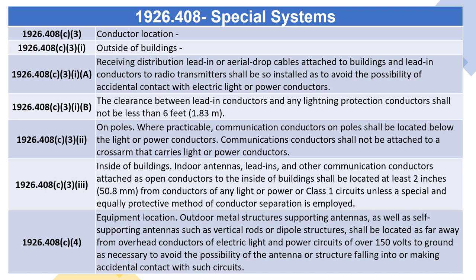1926.408(C)(3) — Conductor Location. 1926.408(C)(3)(i) — Outside of Buildings. (A) Receiving distribution lead-in or aerial drop cables attached to buildings and lead-in conductors to radio transmitters shall be so installed as to avoid the possibility of accidental contact with electric light or power conductors. (B) The clearance between lead-in conductors and any lightning protection conductors shall not be less than 6 feet (1.83 meters). 1926.408(C)(3)(ii) — On Poles. Where practicable, communication conductors on poles shall be located below the light or power conductors. Communications conductors shall not be attached to a crossarm that carries light or power conductors.